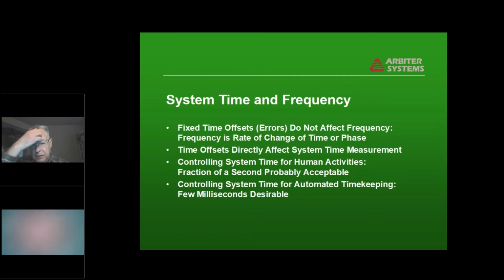For system time and frequency, what we're interested in is really the time offsets between the different locations and the grid. Generally the utilities will try to stay within a few milliseconds offset at midnight, or whenever they start doing their adjustments until 6 in the morning, to start each day more or less on time. And it doesn't stay that accurate over the day with the operation of the power system, but as long as on average it's brought back by 6 in the morning or whatever their target time is, they're okay. And that requires a few milliseconds. That, as I said, is one of the original applications for the GOES time clocks.